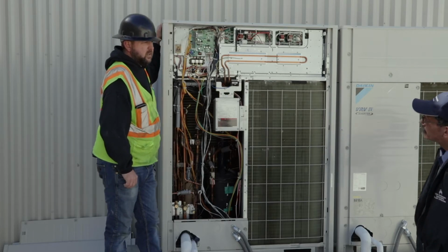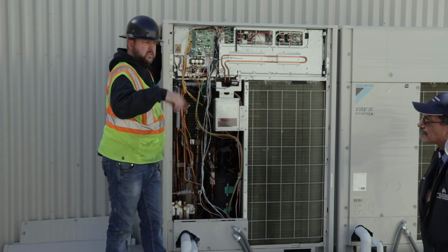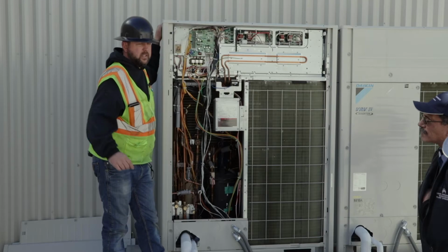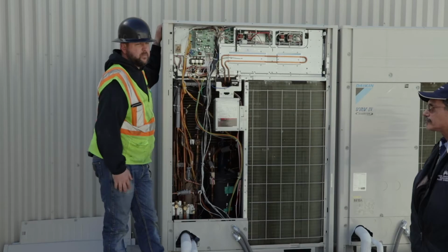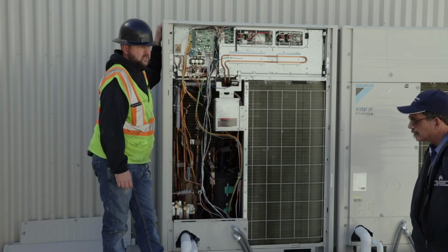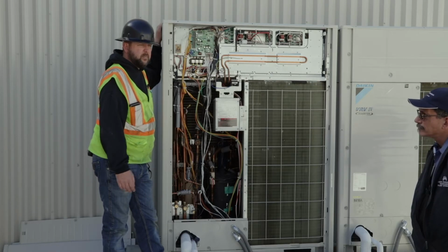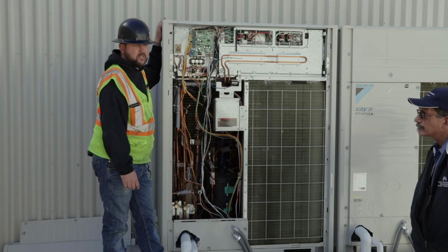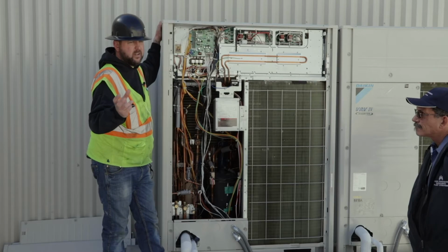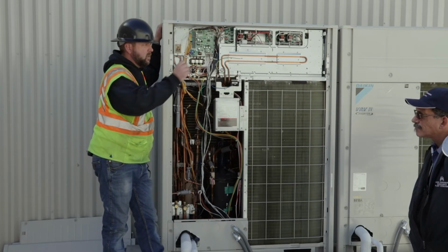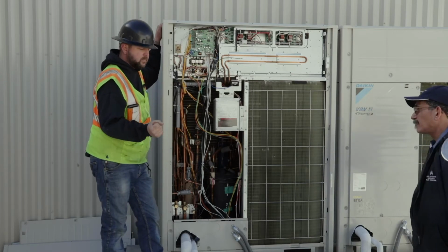Now, when you're doing maintenance on those fan coils, if you turn power off to one fan coil, it's going to alarm that whole system. It will shut down that whole system. It'll throw a comm failure. So, good thing is there's not much to those, other than the washable filters on them. You know, take them out, wash them, that's about it. They do have the external mounted condensate pump. So, like on that little one over there, that's just a 1-to-1.